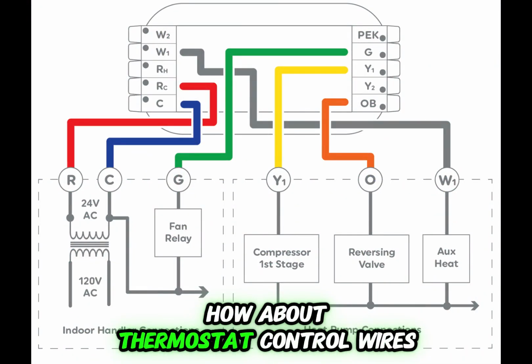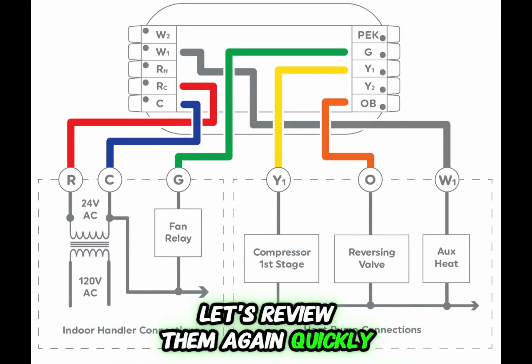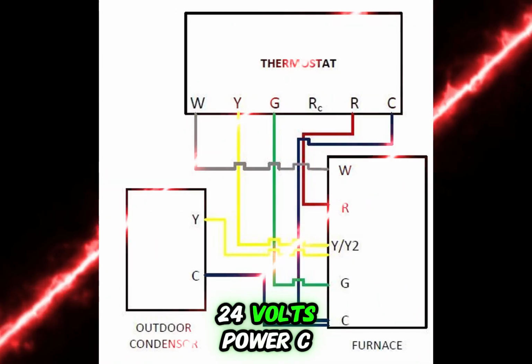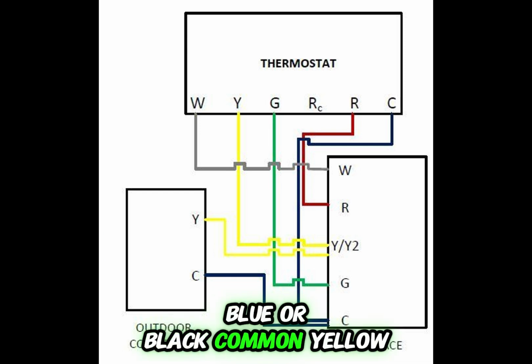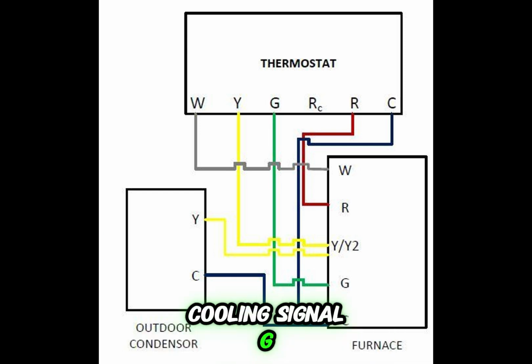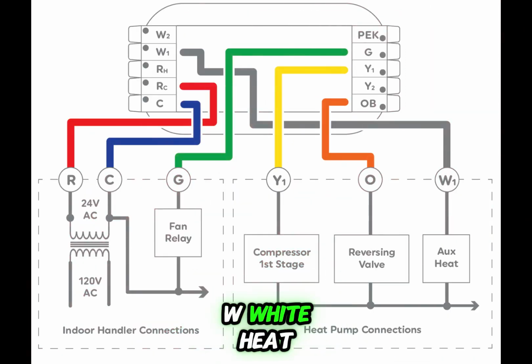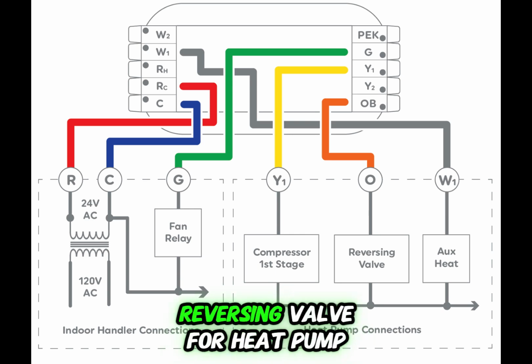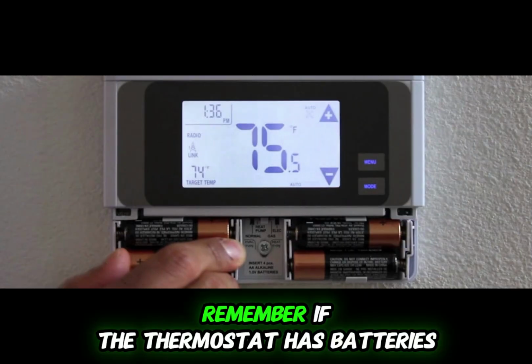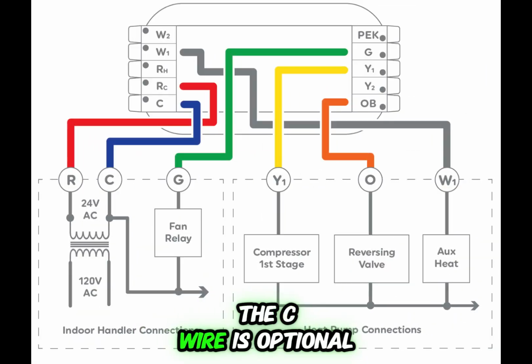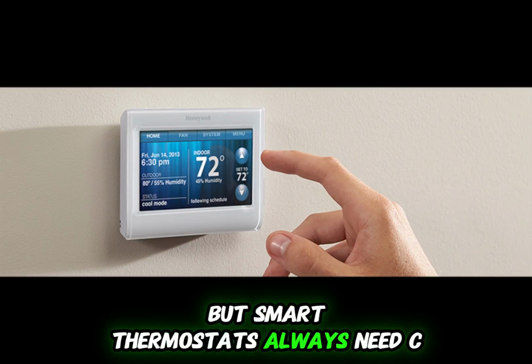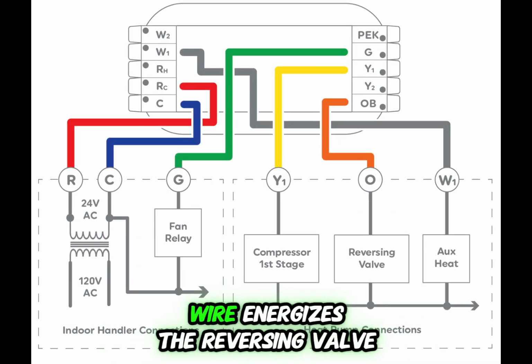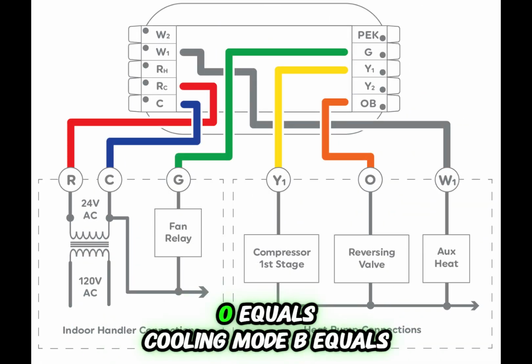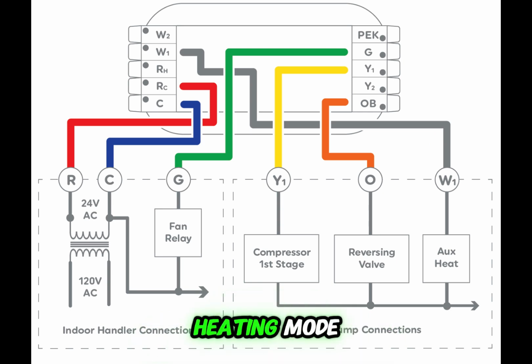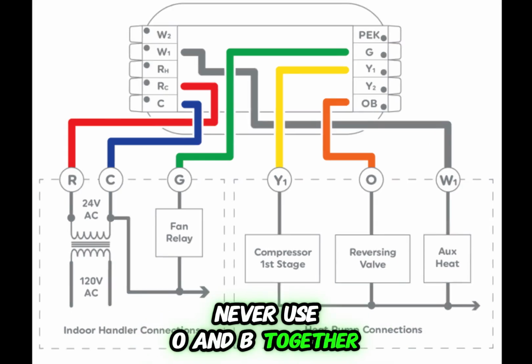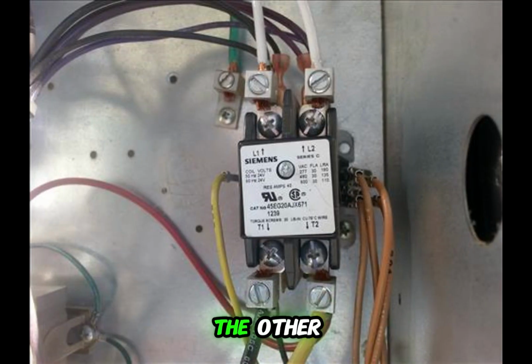How about thermostat control wires? Let's review them again quickly. R, red, 24 volts power. C, blue or black, common. Y, yellow, cooling signal. G, green, blower. W, white, heat. O or B, orange or blue, reversing valve for heat pump. Remember, if the thermostat has batteries, the C wire is optional, but smart thermostats always need C, and the O or B wire energizes the reversing valve. O equals cooling mode, B equals heating mode. Never use O and B together. Your system is either one or the other.